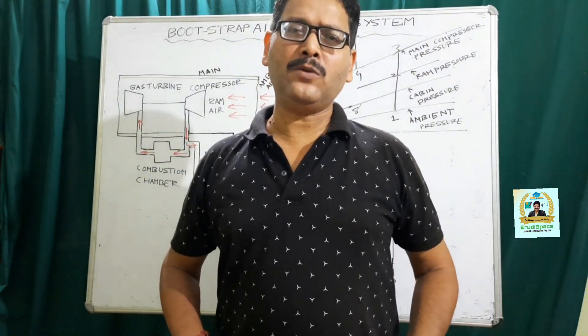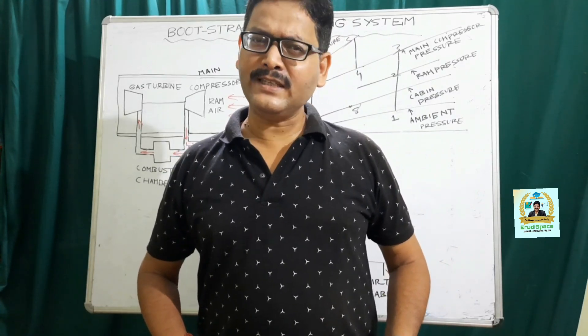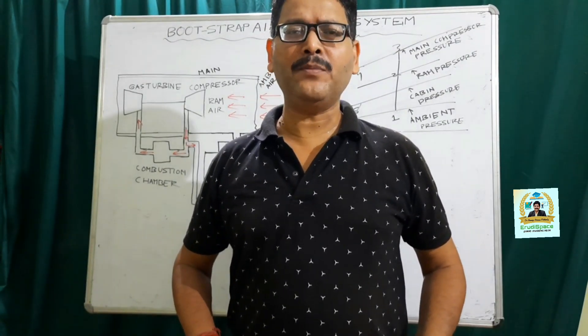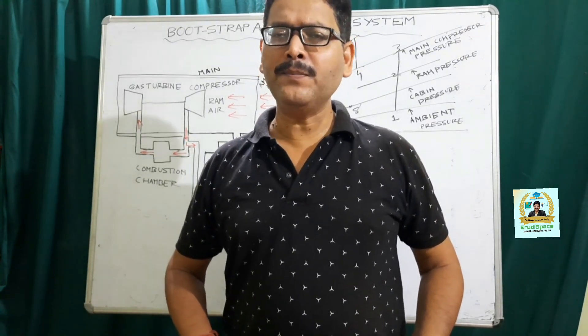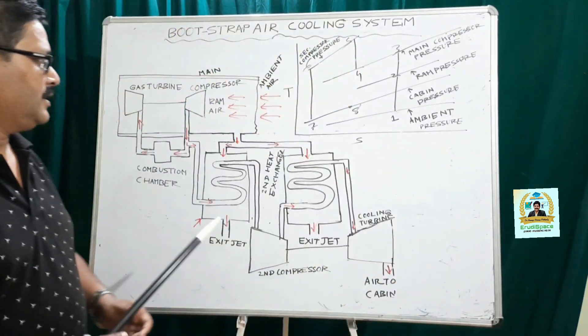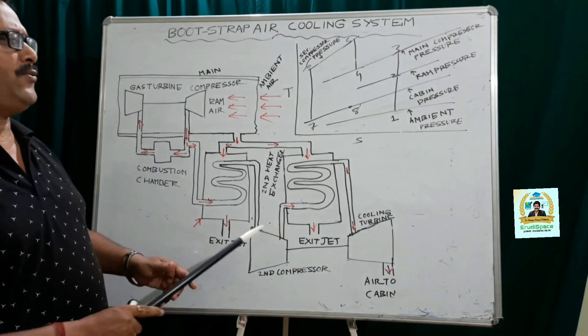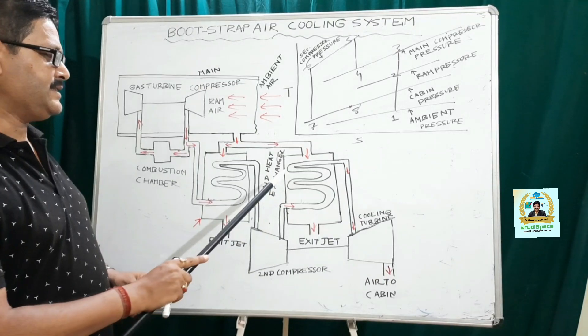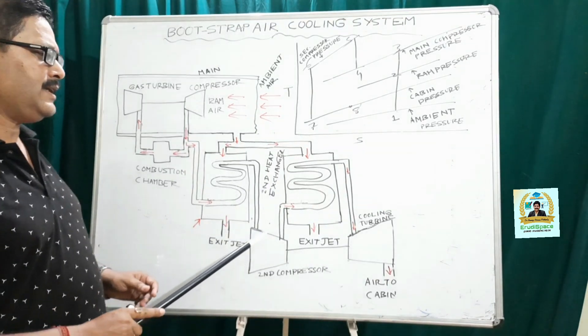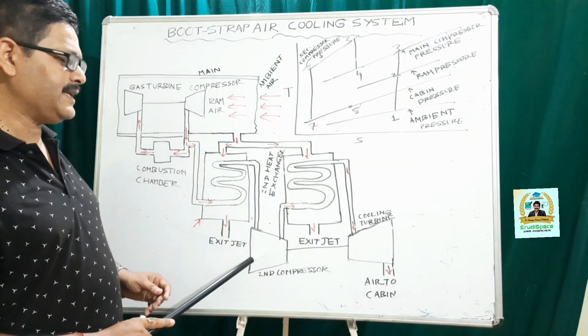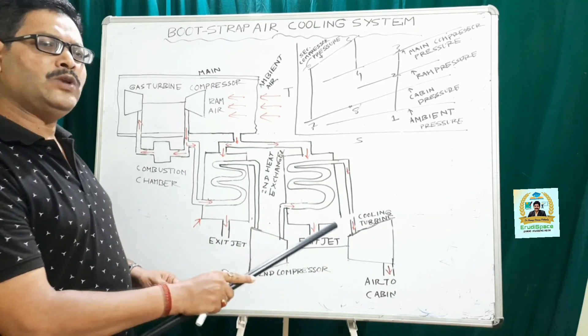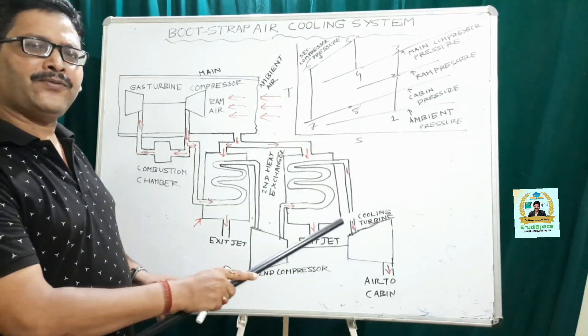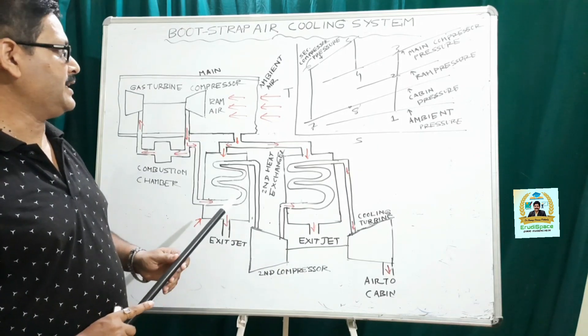The bootstrap air cooling system finds extensive application in transport aircraft and it is actually a modification of the simple air cooling system. So it has all the components of the simple air cooling system, apart from that it does have a second heat exchanger and a second compressor. The cooling turbine instead of driving a fan actually drives the second compressor.